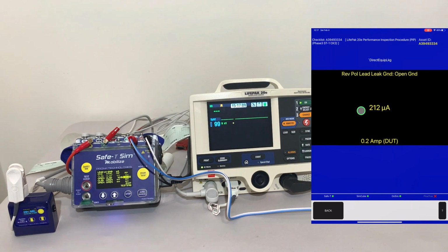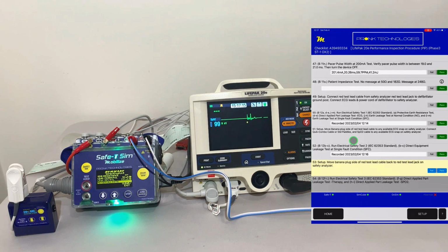And then it's going to, again, show you the current being drawn by the device under test. So it's going to run through all those tests we need to do. And I've confirmed that all of the tests passed or failed. Any tests failed, it would say fail here, but they all passed. And so now we've completed the second test.